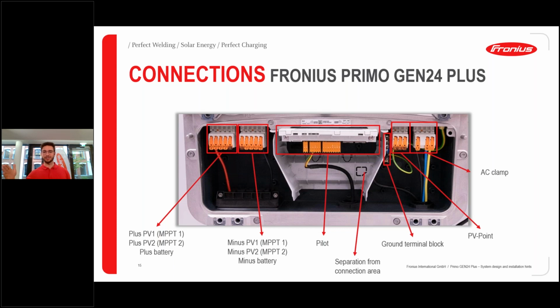And right on the side of this separation, we can see, very unclear in the background, a ground terminal block. So this is actually the only place in the inverter right now regarding the connection area where we have a screw terminal. It's a copper bar with 10 and 16 square millimeter cable connection points with a screw. This is for the grounding.